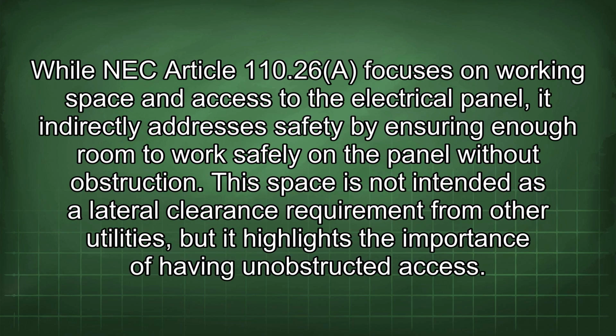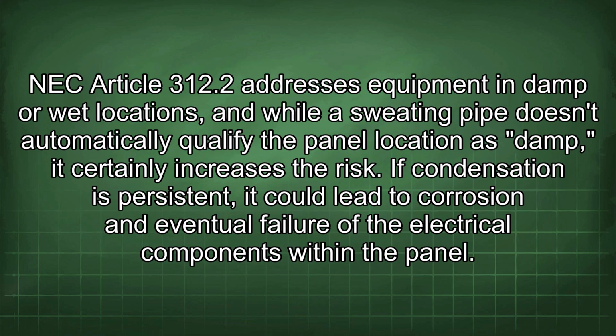While NEC Article 110.26 focuses on working space and access to the electrical panel, it indirectly addresses safety by ensuring enough room to work safely on the panel without obstruction. This space is not intended as a lateral clearance requirement from other utilities, but it highlights the importance of having unobstructed access. NEC Article 312.2 addresses equipment in damp or wet locations, and while a sweating pipe doesn't automatically qualify the panel location as damp, it certainly increases the risk. If condensation is persistent, it could lead to corrosion and eventual failure of the electrical components within the panel.